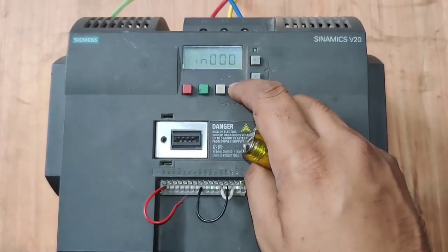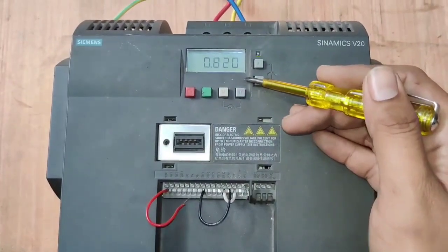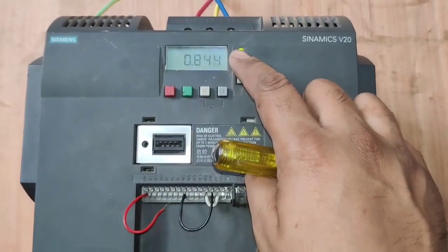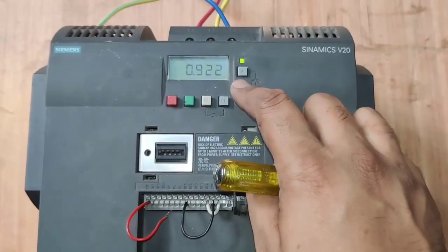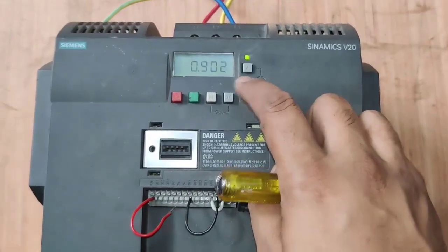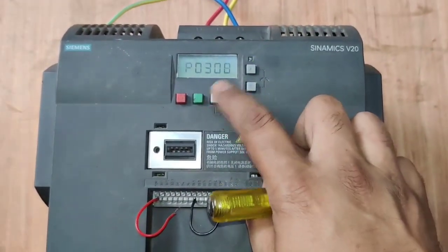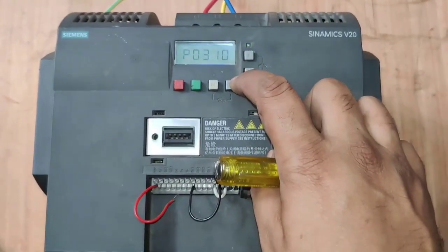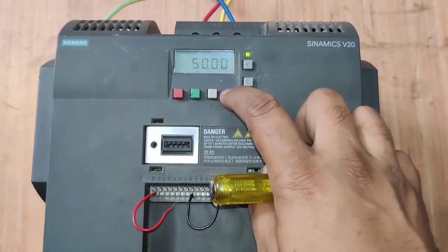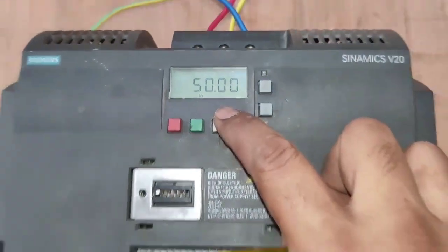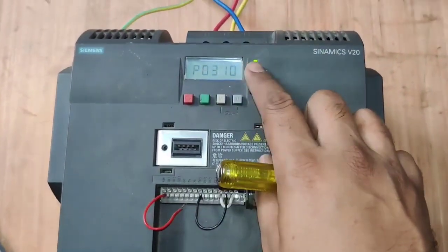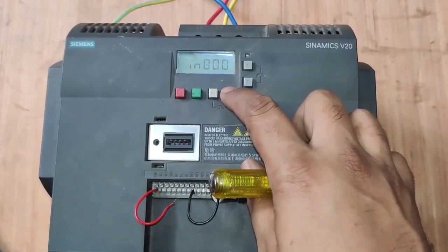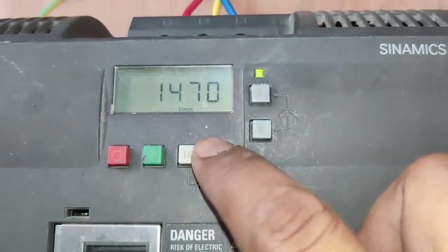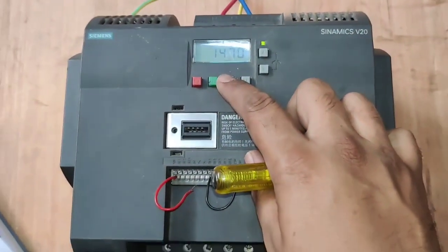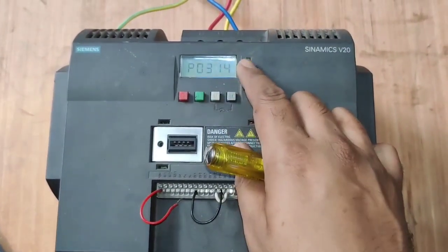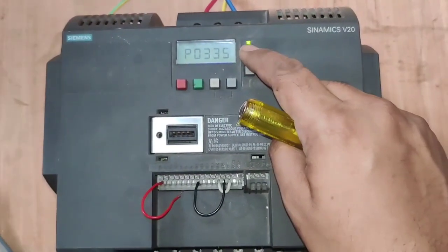Next parameter P308, which is the rated motor power factor. Because the motor is an inductive load, we set the motor power factor to 0.9. Next parameter P310, rated motor frequency. You can see here 50 Hz, because the motor is in India, and in India we have 50 Hz frequency. Next parameter P0311, rated motor RPM. So we set 1470. All these parameters you can see on your motor nameplate, where you can find all the details.